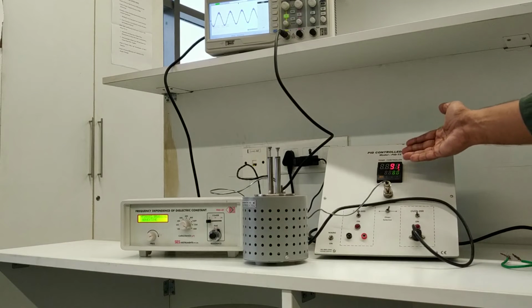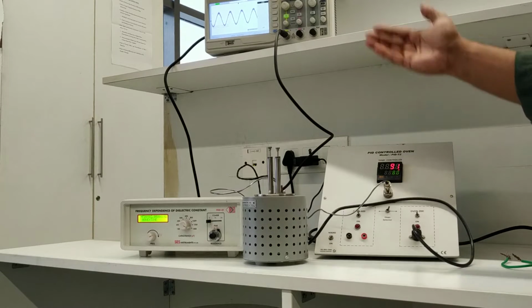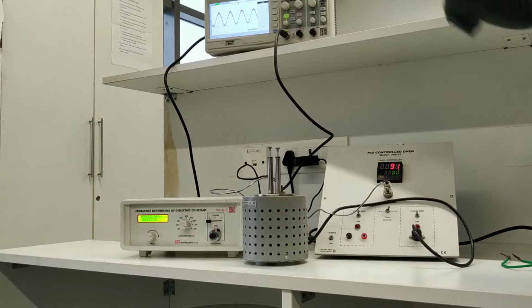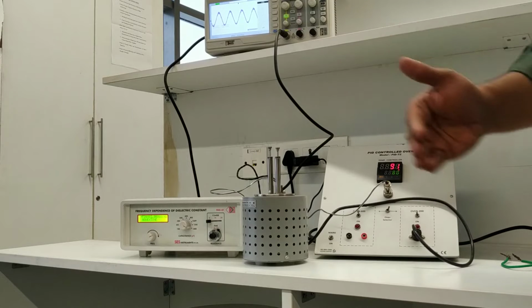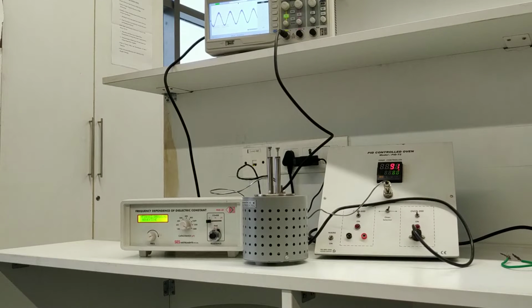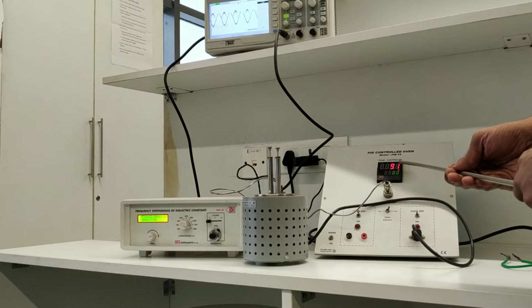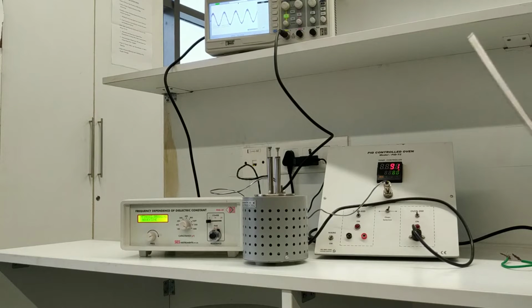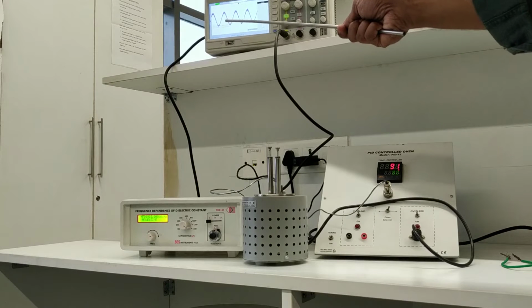Also, this is the temperature at the sensor, so the temperature at the sample might be a little bit lesser than this one, because the heat flow has to happen and the temperature equilibration has to reach there. So anyway, you have to allow it 5-10 minutes to go to equilibrium, so that you get the value that you have set. So let's say it has gone to equilibrium. Now you see there is quite a strong signal.